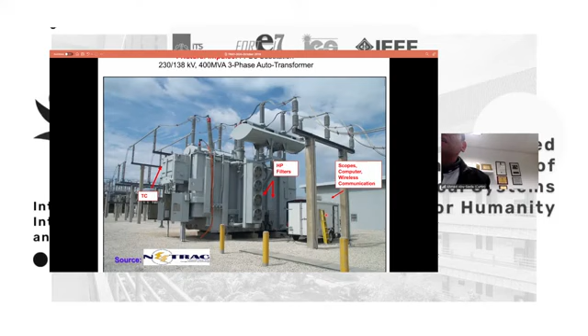People in industry in Florida started thinking about this with an auto transformer that has a tap changer and high pass filters. They brought their measurement devices and scopes, but didn't connect anything externally. They just connected their scopes and tried to use the natural lightning impulse as a source for the FRA, so they wouldn't have to connect to an external source. And they were successful.